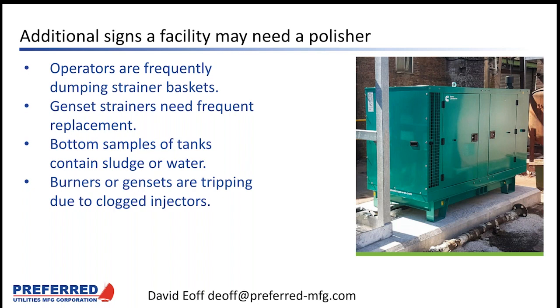We had a facility in New York City recently that actually had a duplex strainer, so they had two strainer baskets, and one of them was completely clogged, so they switched over to the other strainer basket. It didn't take long for that one to completely clog, and then once that strainer basket was clogged, the pumps couldn't get any oil, and the burners tripped on low oil pressure. Our technicians did a bottom sample on their tank, and it was absolutely full of sludge. So these are all issues that a fuel polisher will likely fix.